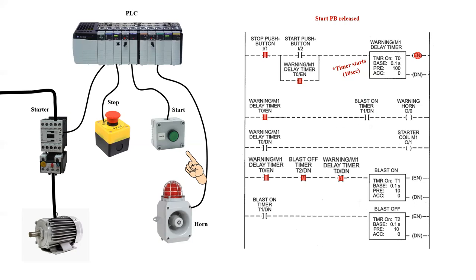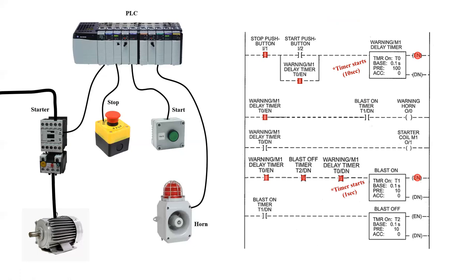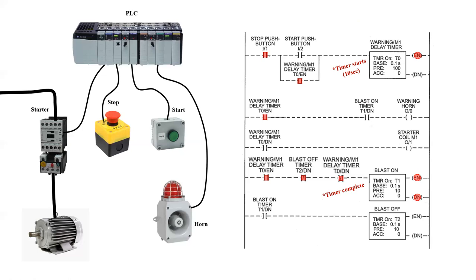So what happens next? If we look at the fourth rung, we can see a complete line of true input instructions, meaning that the blast on timer should start timing. Now it's a very short timer of only one second. And we'll notice that the enable will energize immediately, and it will then complete its time after one second, and the done coil will then go on.